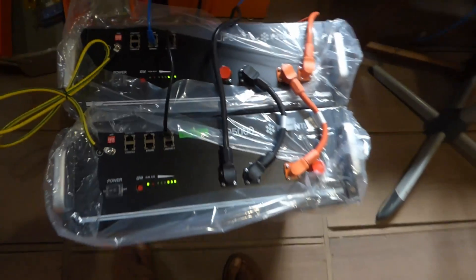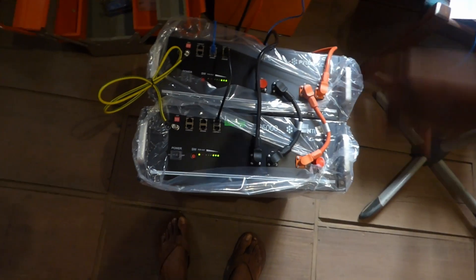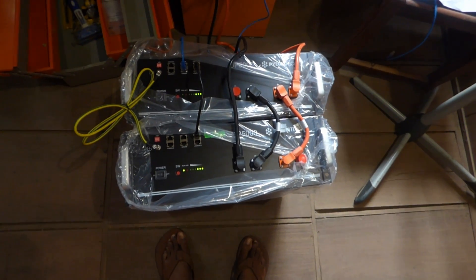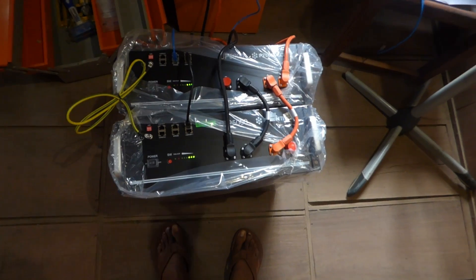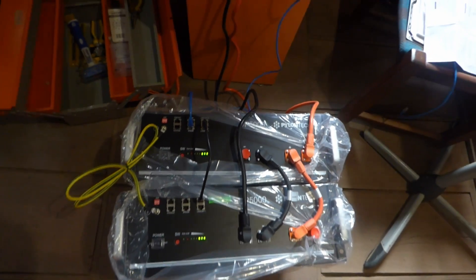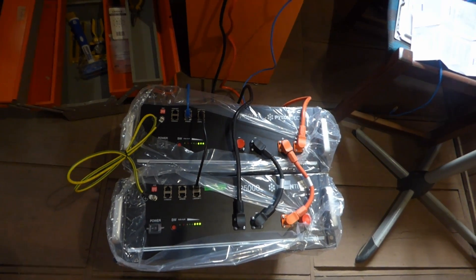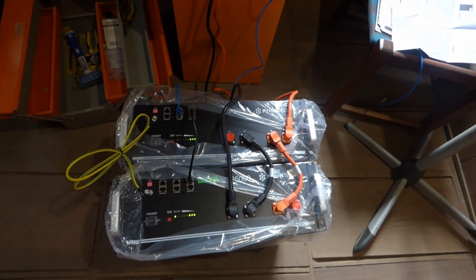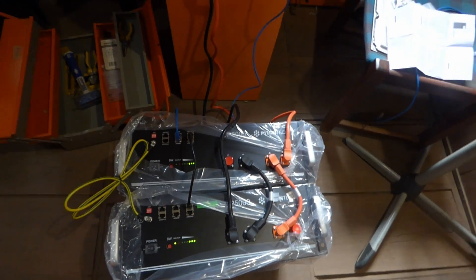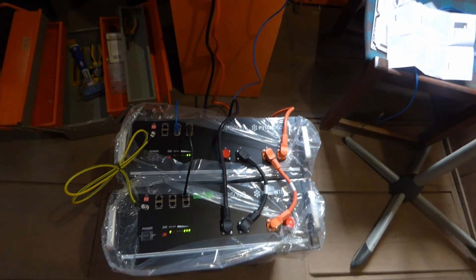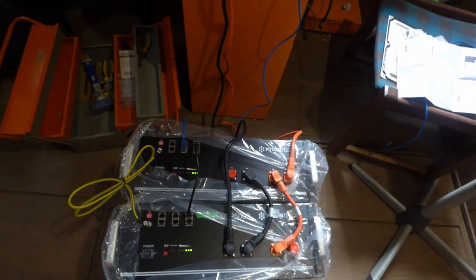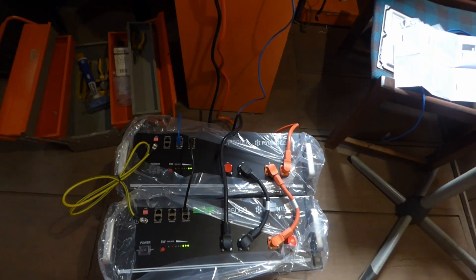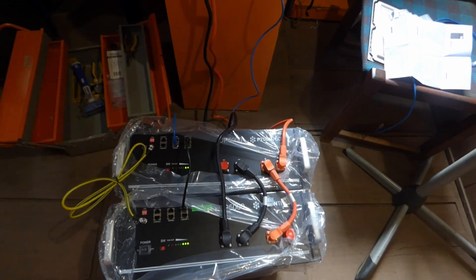So if you recall my batteries, my battery is pretty big. These two here are equivalent to my batteries. And the beautiful thing about this is I can discharge it to 95%. Pylontech allows that we can discharge it to 95%. So now we are giving our customers 90% of the battery capacity, which is mind blowing. So to give you perspective, to get the equivalent 12 volt 200 ampere batteries, I'll need 8 of those.